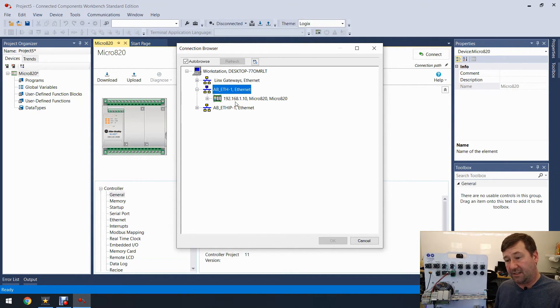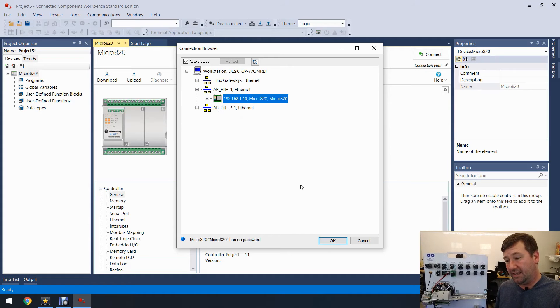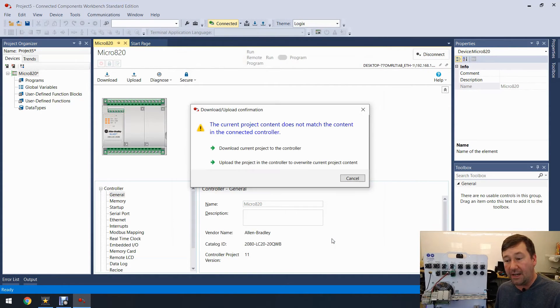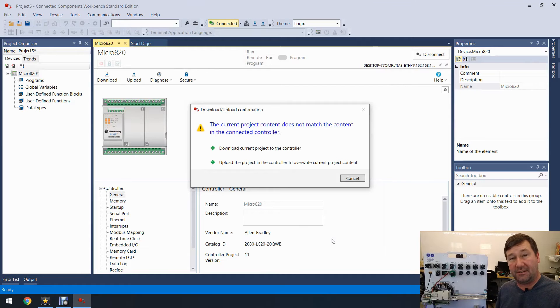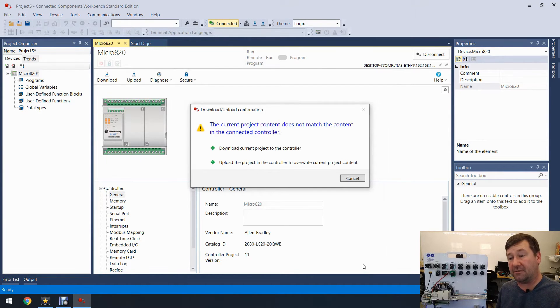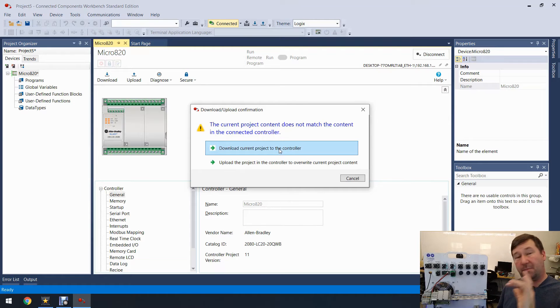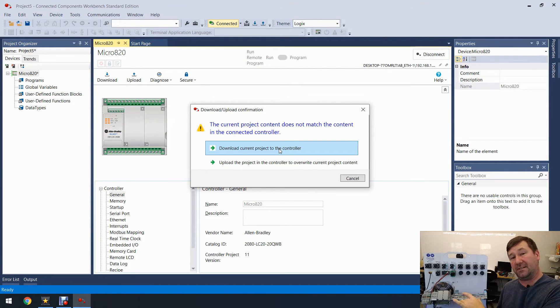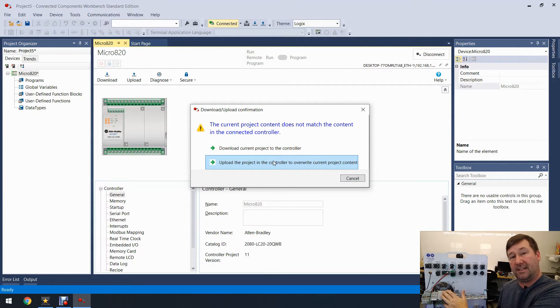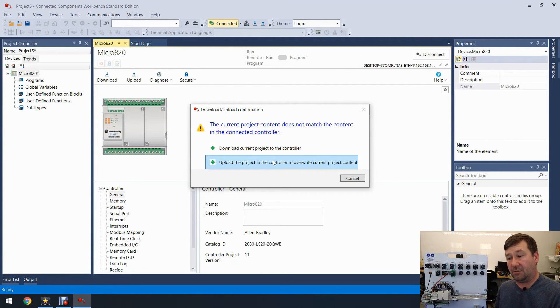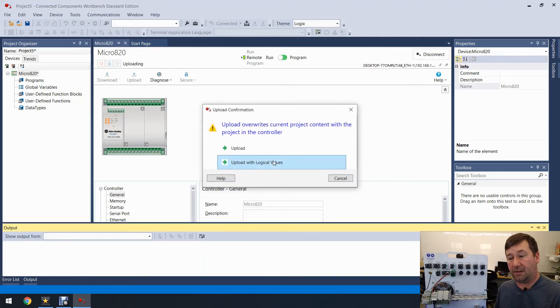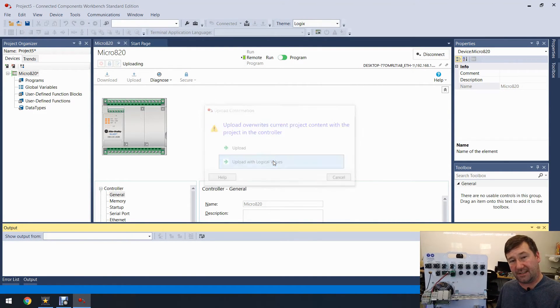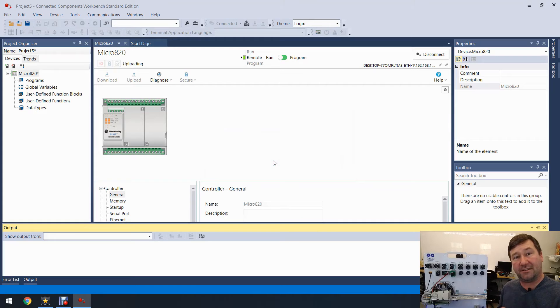We'll go ahead and just click on the Ethernet Devices one, click OK. All right, so now you have the option. It knows that it doesn't have the right program, so you can either download the program that's in the Connected Components Workbench, remember you download from the PC to the PLC, or you can upload the program from the PLC to the PC. So we're going to do that. We're going to upload it and we're going to pull the logical values out of it too, and that's the values that change, the variables.